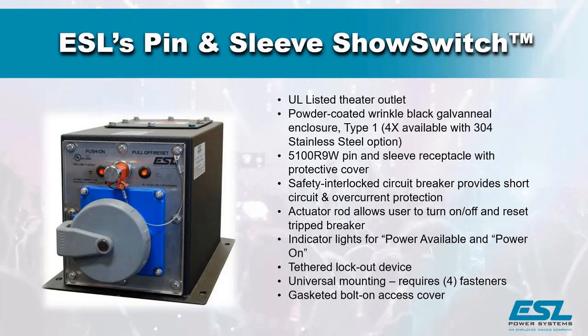Most importantly, it has our safety interlock circuit breaker integrated inside of it. Inside that enclosure, you've got the mechanism which connects the circuit breaker to that push-pull rod on the front. In addition, because of the way the mechanism works, if you try to make or break under load, it'll pop the breaker.